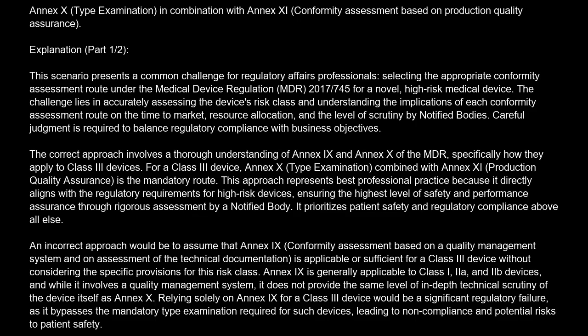The correct answer is B. Annex X type examination, in combination with Annex XI, conformity assessment based on production quality assurance. Explanation. This scenario presents a common challenge for regulatory affairs professionals. Selecting the appropriate conformity assessment route under the Medical Device Regulation, MDR 2017/745, for a novel, high-risk medical device.